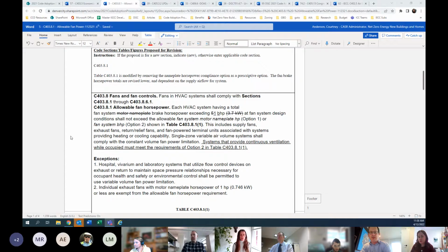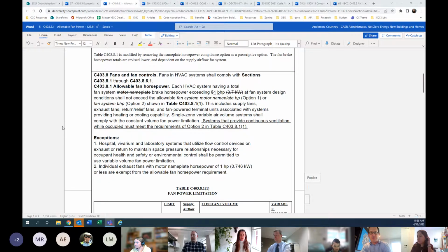So the 2 types of changes we made, one change is to simply lower the fan power limit for these systems. So it could be either brake horsepower or related to the system static pressure. And then the second change is to expand the scope of these requirements. If you notice that the C403.8.1, the typical limit is that these requirements only impact systems with brake horsepower exceeding 5 brake horsepower at design conditions, and we're expanding the scope to lower that down to 1. So this brings in a lot of the somewhat more modest sized systems that previously were not directly regulated.